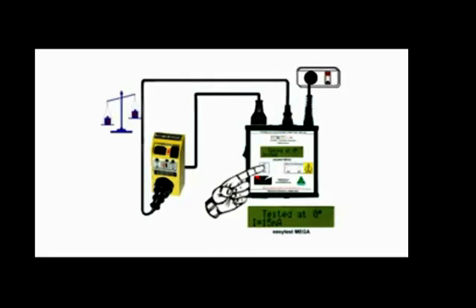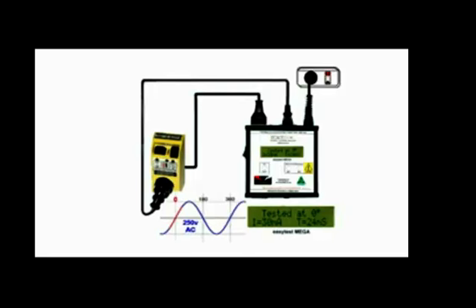Press the start button and a 15 milliamp load is applied for 1/3 of a second. If it fails to trip, that's a pass. So the Mega automatically applies 30 milliamps and measures the time taken to trip. It should be under 300 milliseconds. In this case, it's 24. That's a pass.